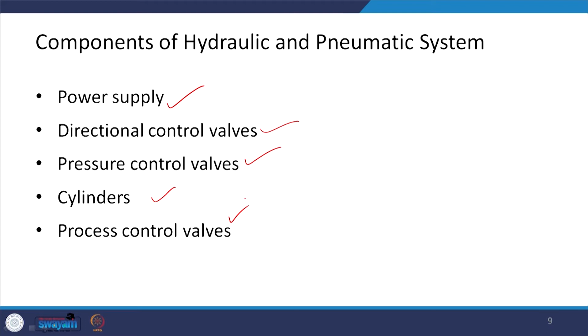First of all, we will be looking at the hydraulic power supply. In the hydraulic power supply, as I said, we are using oil. So, there is a sump where the oil is kept. This oil is pumped with the help of a pump, and this pump is actuated by a motor. Oil from the pump goes to a non-return valve, so that oil does not come back to the sump from this side, and then it goes to a pressure release valve in order to release the excess pressure, and then it goes to the accumulator. Whatever oil is remaining or returning comes back to the sump through the return side, and this cycle can be repeated. In the pressure release valve also, the oil is brought back to the oil sump.